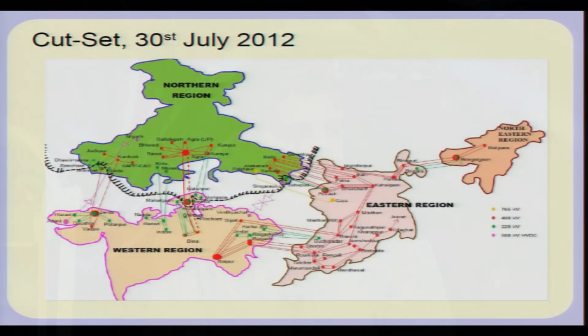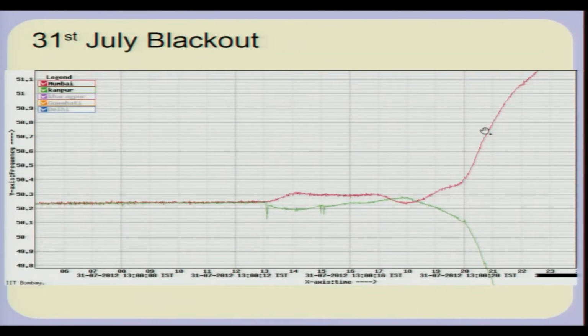Under normal circumstances, you have a swing where there is an increase in the phase angular difference between two parts of the grid, but the transmission lines are able to restore it because of the spring-like action. But if the spring loses its springiness, then you have a situation where you lose synchronism, and this is because the spring is non-linear. If you stretch it too much, it loses its stiffness. So, this is what we saw. In fact, on the very next day there was another blackout, but the pattern was somewhat different. Now, it is not very easy in a nonlinear grid, in a system with many transmission lines, to predict how the cut set or the separation will occur.